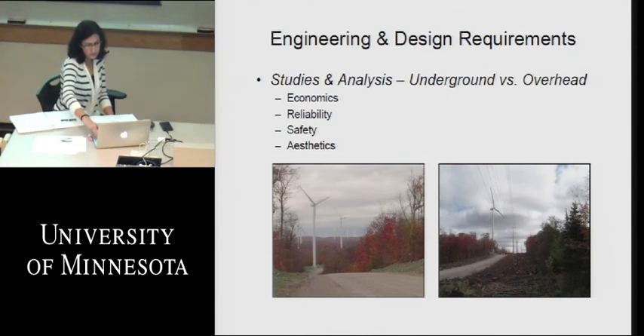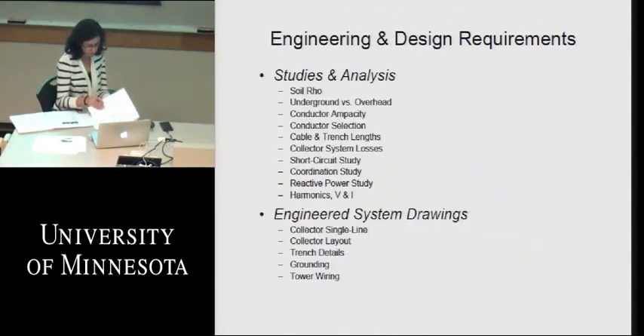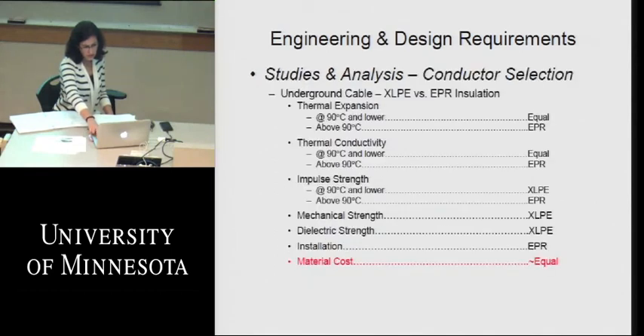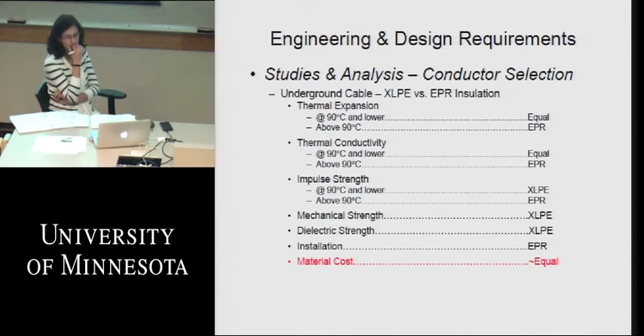Next slide. All the different studies you've got to do for the electrical analysis of the collection system as such, and then all the drawings you need to generate. So I won't go through all those. We're getting only a few minutes to go here. And then for underground constructions, we're using either XLPE or EPR, crosslink polyethylene insulated underground cable, or the rubber type of insulated cable here. This is just an analysis of the two and a comparison of the two.